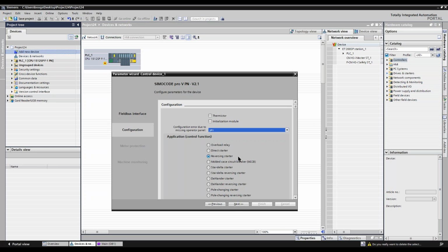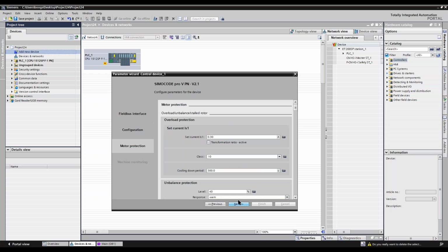Then again, it's asking, are you sure you want to do reversing starter? And you'll learn that with Siemens software. It's like, are you sure? Are you really sure? So it's just giving you a chance to verify. Hit next. Okay, now this is where I put in the full load amps. So for my little demo, I'm going to put in 0.5. That comes off the nameplate of the motor. Full load amps. Okay, and then trip class.